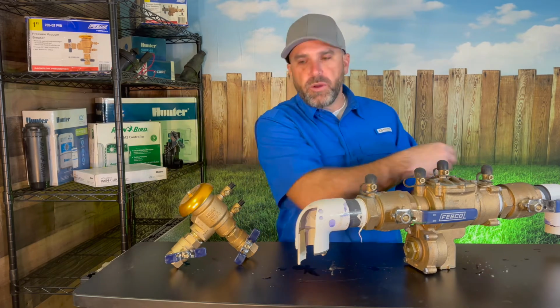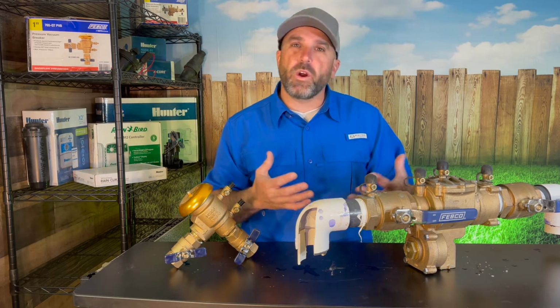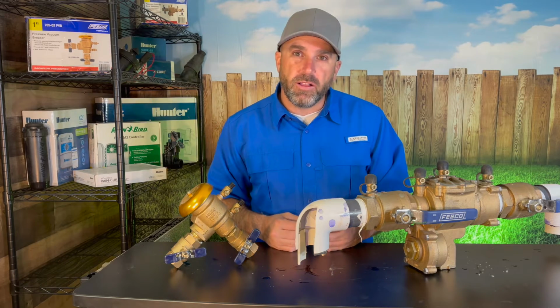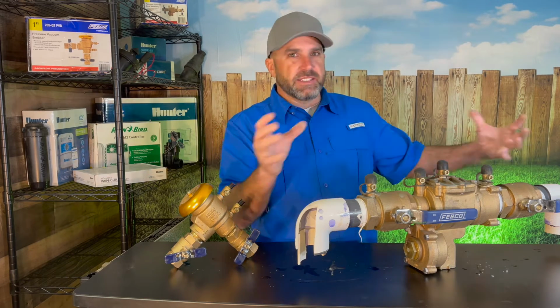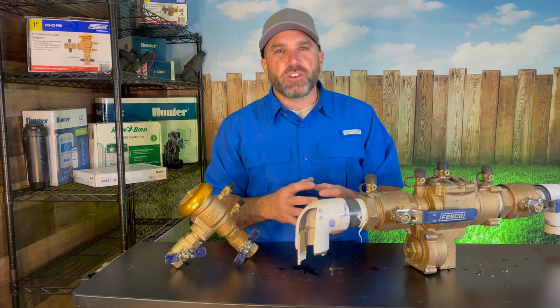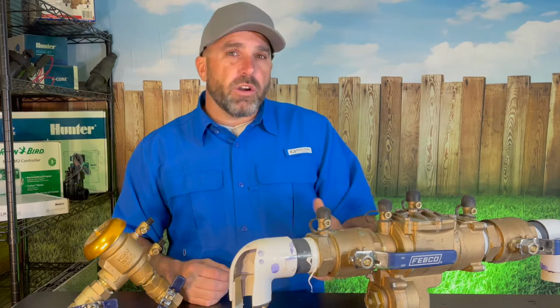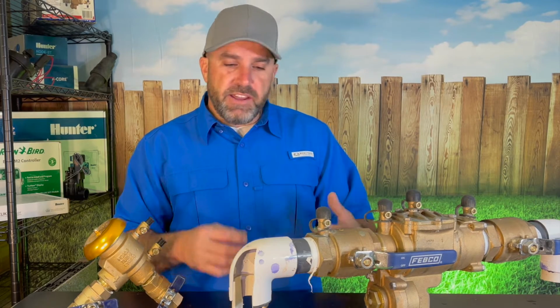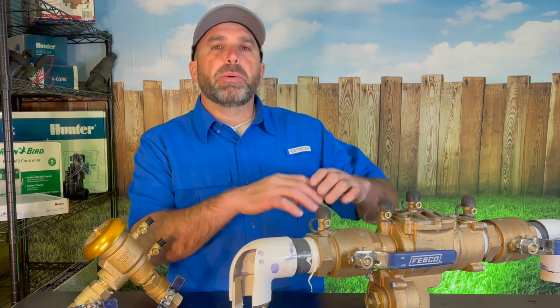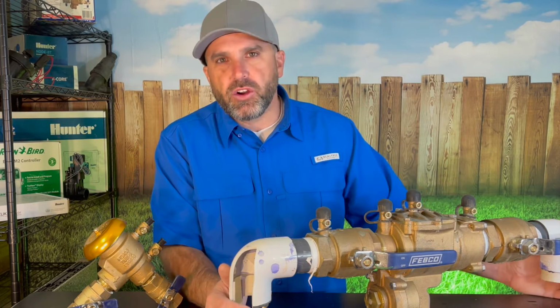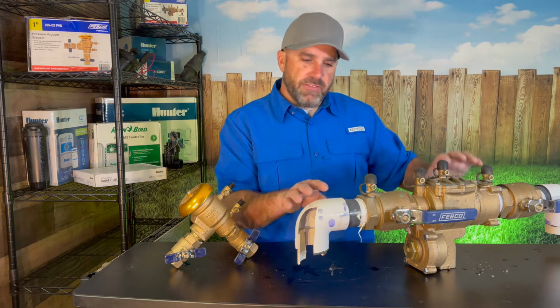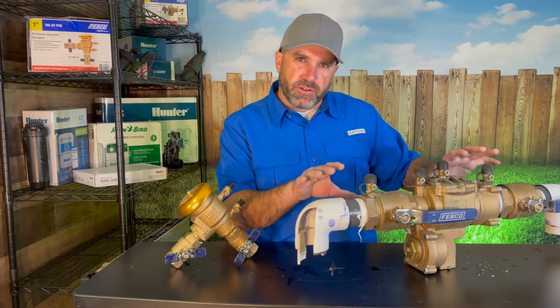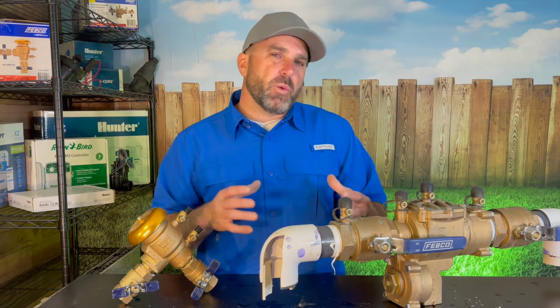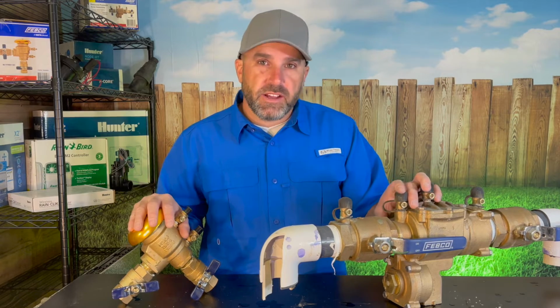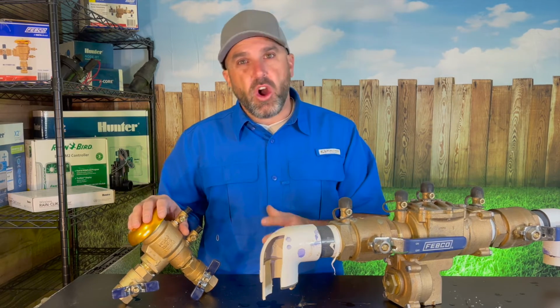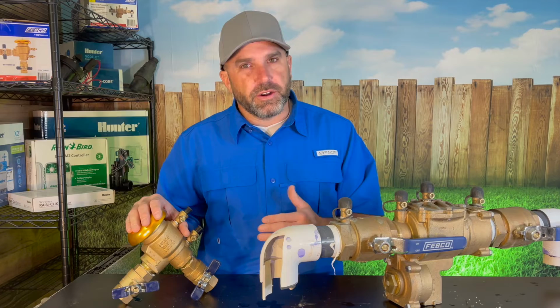You can wrap all the way around this stuff, or you can buy some regular insulation like you'd see in a wall and wrap that up and tape it up and give it some sort of cover and some sort of insulation. Now, one of the things I would recommend, even if you are going to wrap it, is to still put some sort of insulated cover over the backflow device. Having it wrapped and having it covered with an insulated cover is really one of the best ways to winterize your backflow device if you're leaving it on and still wanting to water throughout the winter.